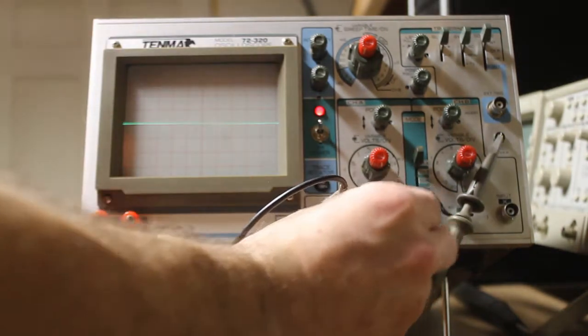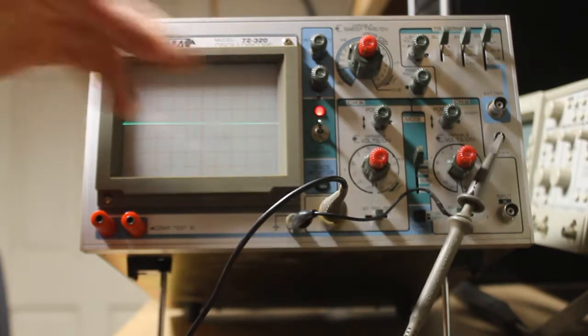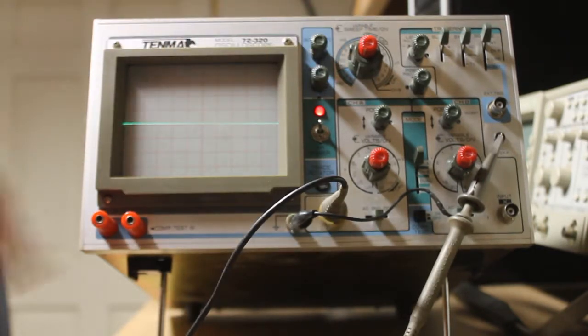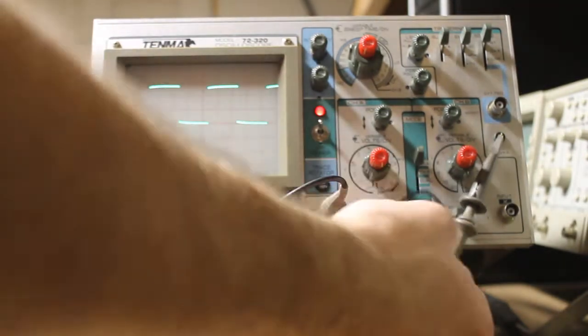Also, when you go to ground display, if your trace is not even across the center graticle, then you can use the trace rotation to correct that. Go ahead and go back to DC display. This is the one we were having trouble with earlier. And as you can see, it's stabilized quite a bit. AC works well as well.